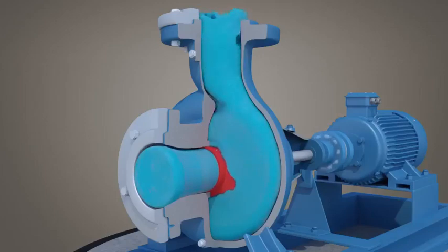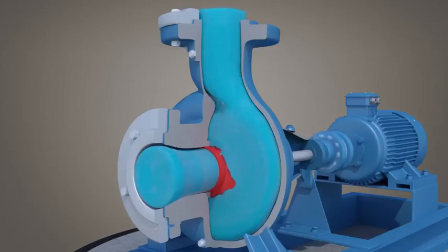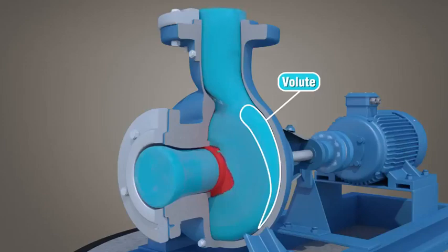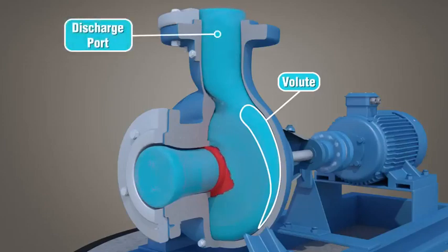As the impeller spins, centrifugal force moves liquid from the eye outward along the impeller blades, toward the inside curved funnel area of the casing, known as the volute. As the liquid travels along the volute, its velocity decreases while its pressure increases. The now higher pressure liquid flows to the discharge port of the pump and out into the piping system.